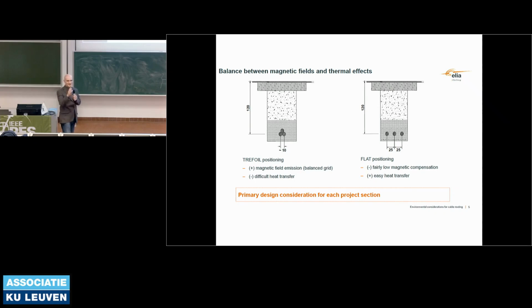It's really fantastic. The 3 conductors are so close to each other that you won't notice any magnetic field radiated from the cable, especially at a meter or two, because the currents producing these magnetic fields cancel out immediately since they're so close. Remember overhead lines? With a field meter you'd only measure the magnetic and electrical field of the lowest conductor if you were directly under it. For trefoil positioning, it's almost perfect.